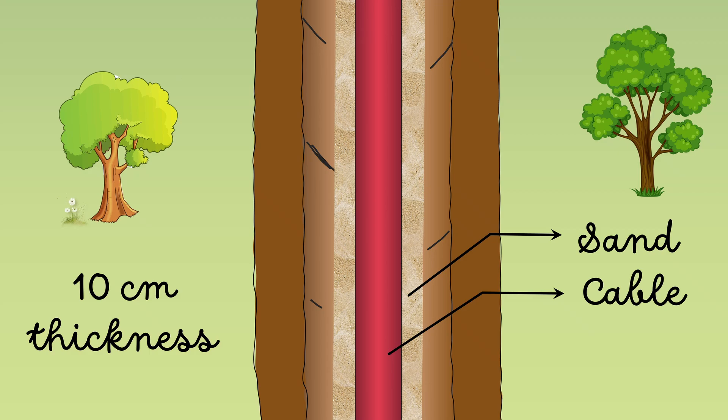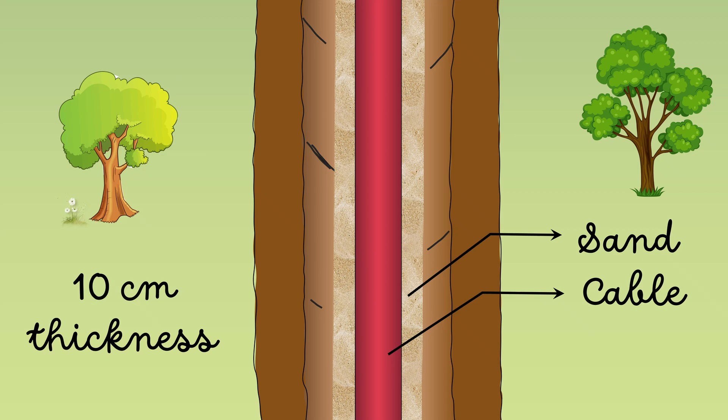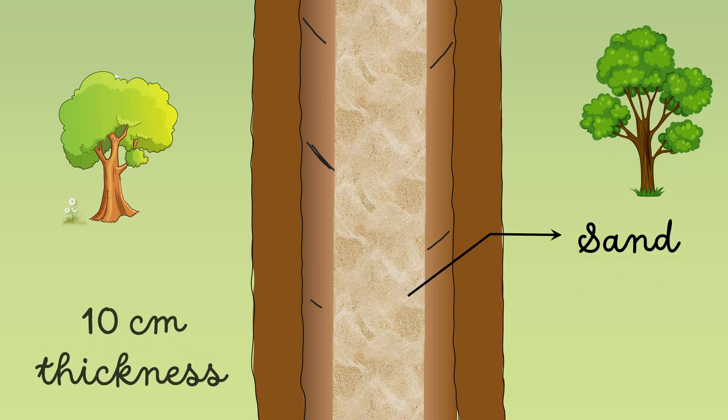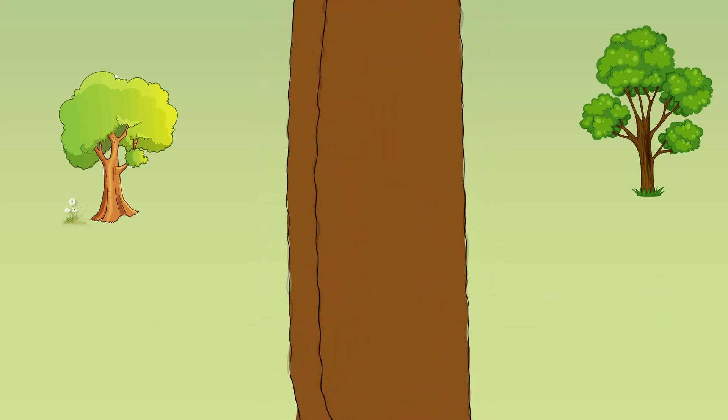The sand prevents the entry of moisture from the ground and thus protects the cable from decay. After the cable has been laid in the trench, it is covered with another layer of sand of about 10 centimeter thickness. The trench is then covered with bricks and other materials in order to protect the cable from mechanical injury.